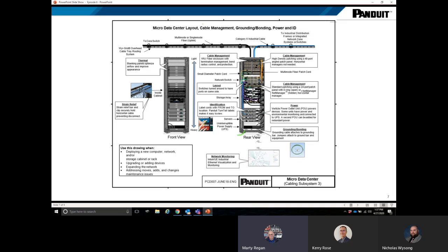This layout strategy mitigates the risk involved with a less organized solution and reduces network interruptions resulting from common cabling problems. Examples would be difficult to access input-output copper and or fiber cables, patch cords that snag when pulled front to back, and all the cabling crisscrossing would increase the thermals inside the cabinet.